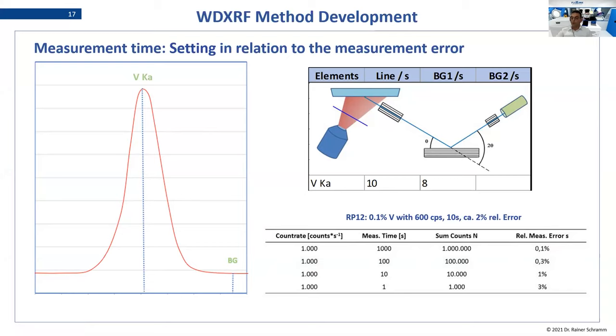A final question: does Fluxana offer a general oxide package calibration set, and does it come with a suitable drift monitor set? Yes — we have a complete package, the Raw Professional I showed you. It comes with three different drift monitors and covers all these elements. It's also very easy to expand the package to elements not standardly included — you would just get five or six more calibration beads and you can expand it.